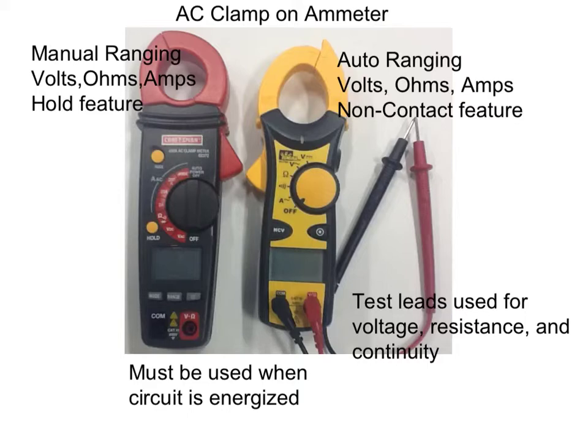And how this meter works is it senses and measures the amount of magnetic field that is going to bleed off of that conductor when we're running AC current through it. And inside of this is a current transformer that's capable of measuring that magnetic field. We've got some circuit board capabilities inside the meter. It measures that magnetic field, it automatically does some calculations, and it displays to us on the screen the amount of current that we are drawing on that circuit.